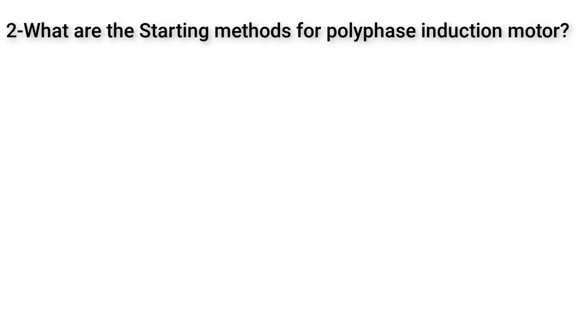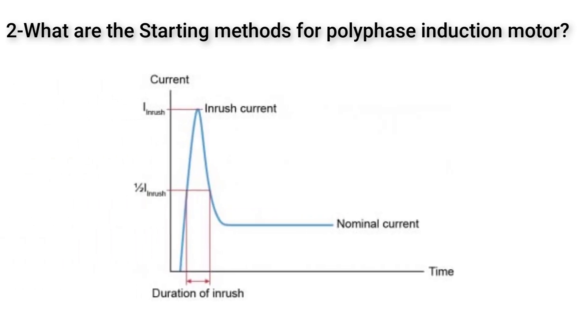The second question here is what are the starting methods for three-phase induction motors? Well, we use different methods of starting induction motor to reduce the applied voltage on the motor windings because any induction motor suffers from high inrush current at starting. This inrush current is equal to 7 to 11 times the full load current which is too much and will cause high voltage drop which will cause under voltage on the system.